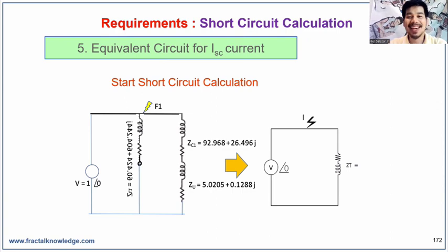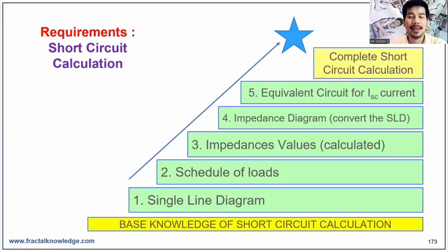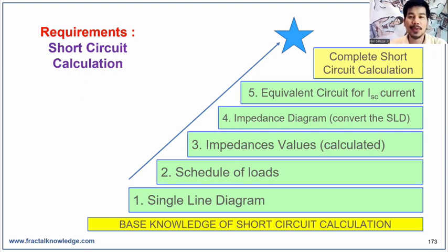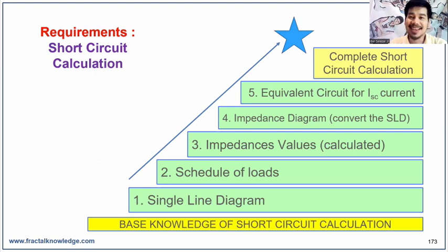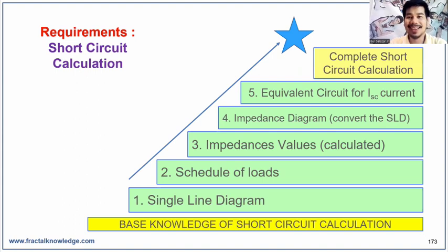The fifth requirement is to simplify the impedance diagram to the fault point reference, to be able to use Ohm's law to calculate the fault current at specific points. To summarize, we covered all the base knowledge of short circuit calculation and the steps required to complete the study: the single line diagram, schedule of loads, calculated impedance values, the impedance diagram converted from the single line diagram, and the equivalent circuit for short circuit currents.